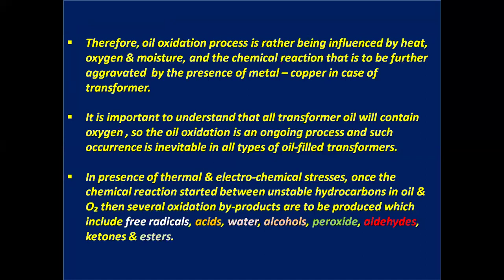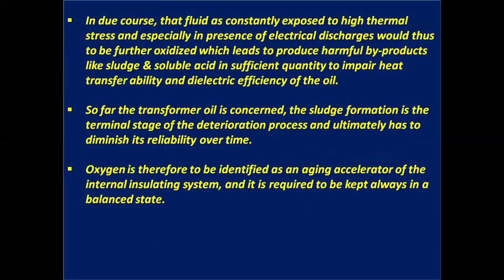In the presence of thermal and electrochemical stresses, once chemical reactions start between unstable hydrocarbons in oil and oxygen, several oxidation byproducts are produced, which include free radicals, acids, water, alcohols, peroxides, aldehydes, ketones, and esters. In due course, the fluid, constantly exposed to high thermal stress and especially electrical discharges, is further oxidized, which produces harmful byproducts like sludge and soluble acid in sufficient quantity to impair the heat transfer ability and dielectric efficiency of the oil.